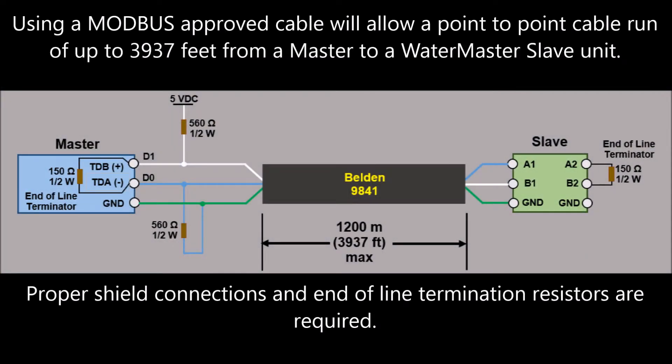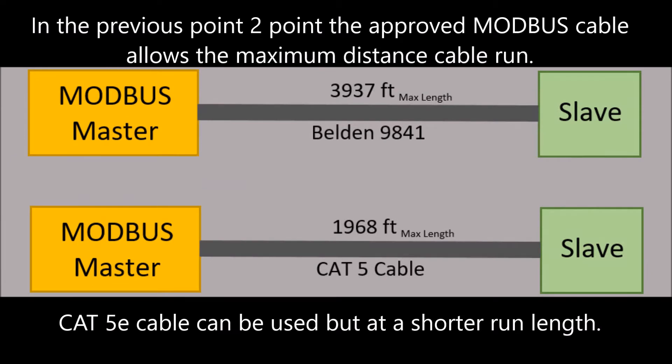Using a Modbus-approved cable will allow a point-to-point cable run of up to 3,937 feet from a master to a Watermaster slave unit. Proper shield connections and end-of-line termination resistors are required. The approved Modbus cable allows the maximum distance cable run, while CAT-5E cable can be used but at a shorter run length.